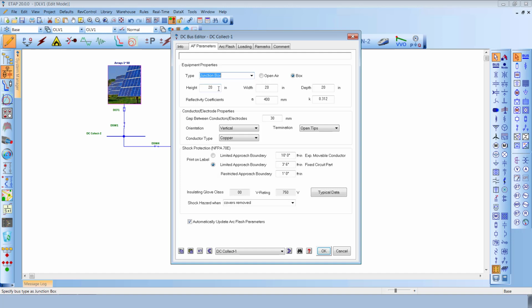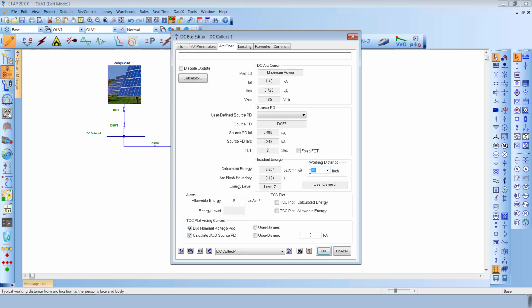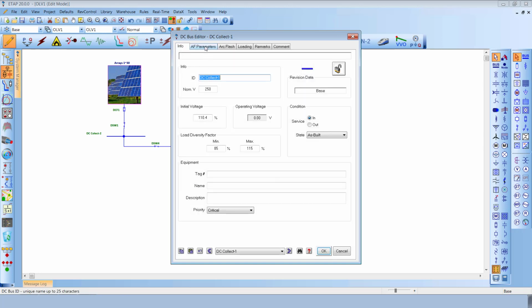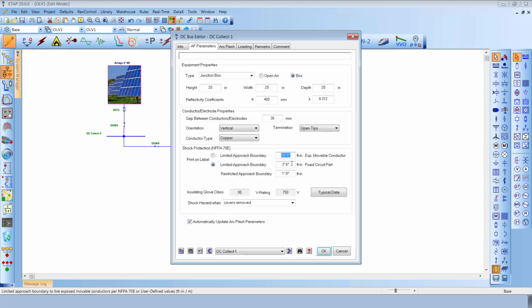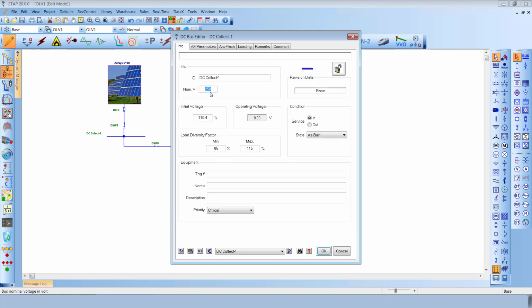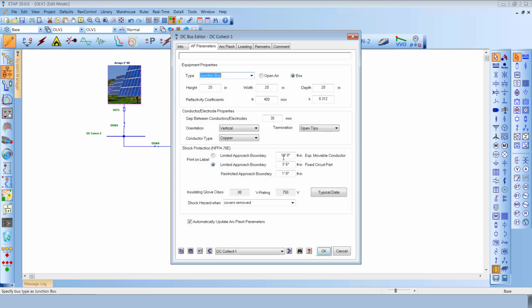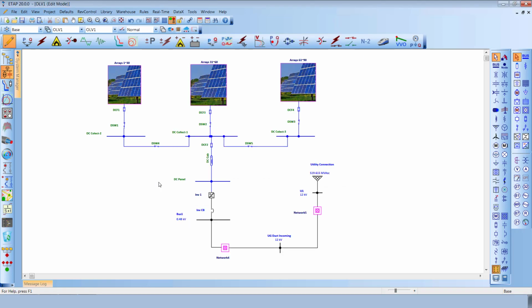Here, the user could enter the height, width, and the depth of the box along with the gap between the conductors and electrodes, and enter the working distance in the arc flash page respectively. ETAP automatically populates the shock protection boundaries based on the corresponding nominal voltage entered in the info page according to the NFPA 70E tables.